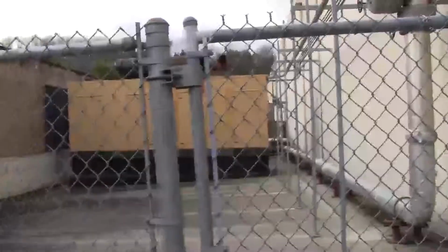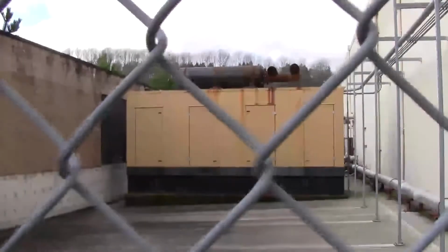So, that is the generator. Oh, that's the generator. Yes. So that is independent of the power source, so that if that power source goes down, this thing kicks in? Yes. That is what the automatic transfer switch is for. When the utility power goes down, the automatic transfer switch says, okay, 13 seconds after the utility power goes down, the generator will spin up. The generator spins up within 13 seconds and starts transferring power into the facility. 5 seconds after the generator kicks on, the UPSs are back on clean power.